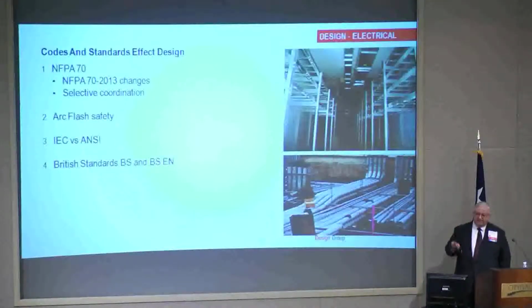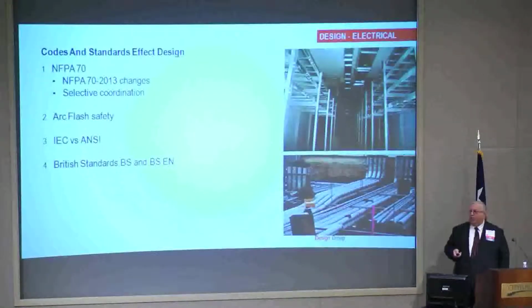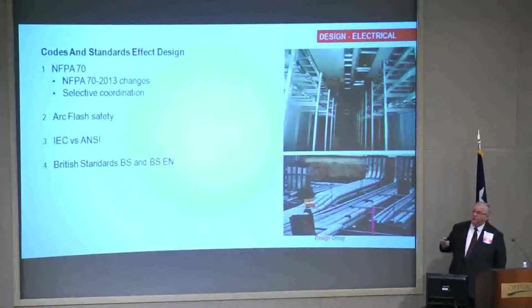IEC versus ANSI. ANSI is an American standard. We tend to overbuild our equipment in the eyes of IEC. For instance, a motor starter that we would have that would be ANSI rated would be good from 1 to 10 horsepower. In the IEC world, that would be 5 or 6 different starters. They tend not to overbuild. We tend to build tanks. IEC tends not to. So that's another issue you need to be aware of as you go from country to country as to what standard they're following. They're both appropriate when applied appropriately. You just need to know that. Sizes do change and availability changes.